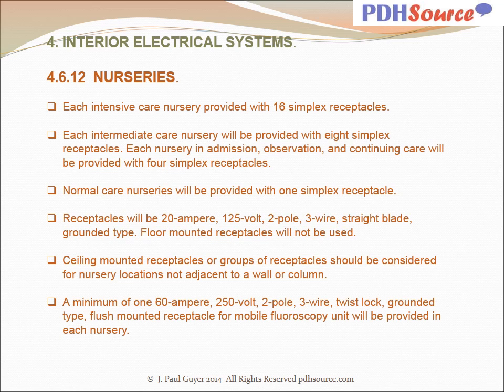Receptacles will be 20 amp, 125 volt, 2 pole, 3 wire, straight blade, grounded type. Floor mounted receptacles will not be used. Ceiling-mounted receptacles or groups of receptacles should be considered for nursery locations not adjacent to a wall or column. A minimum of one 60-ampere, 250 volt, 2-pole, 3-wire, twist-lock, grounded type, flush-mounted receptacle for mobile fluoroscopy unit will be provided in each nursery.